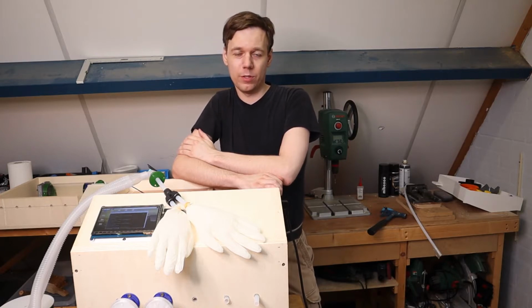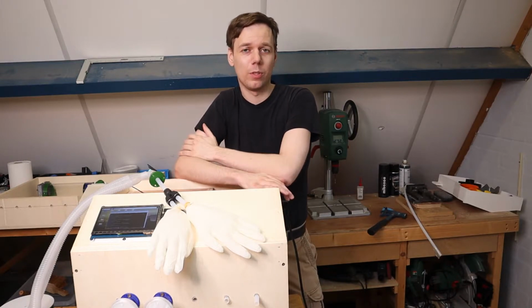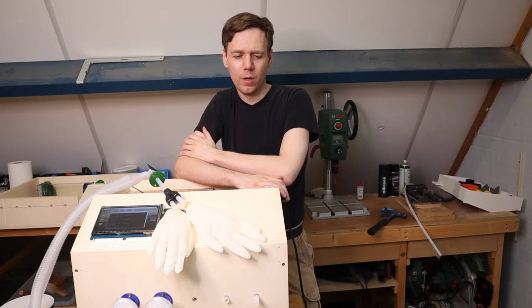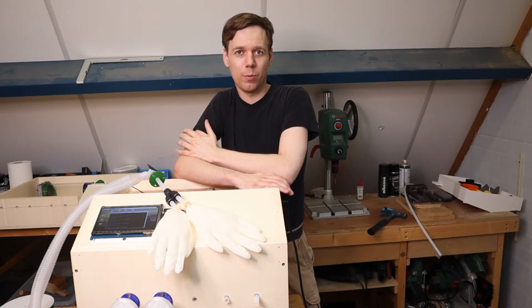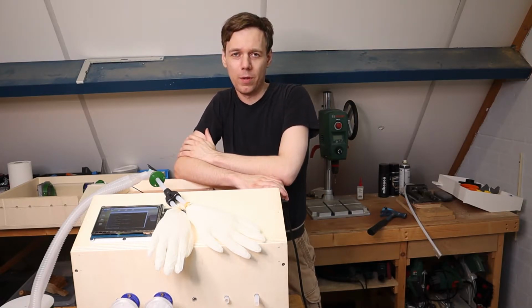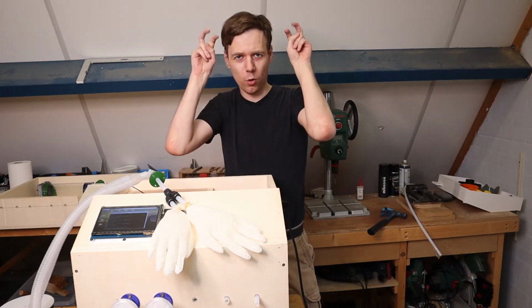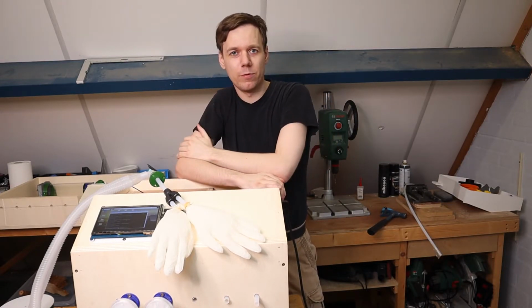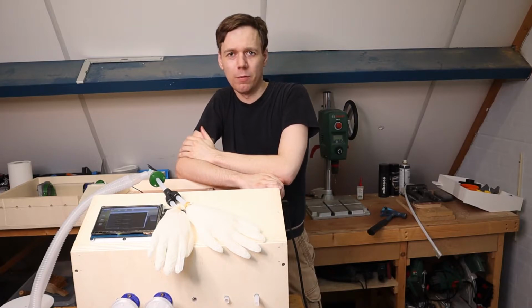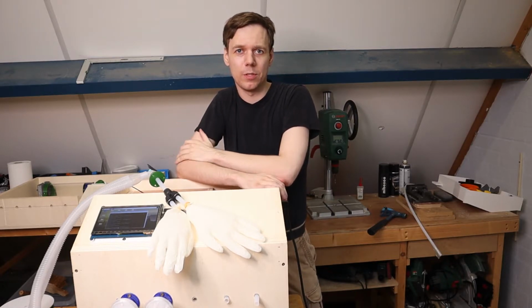The flip side of this is that ventilators are usually constructed out of custom bespoke components, because that's what gives you the best performance. However, if you try to ramp up production, you run into the issue that the parts simply aren't there. Remember when Medtronic open sourced their PB560 ventilator? None of them were built. None. The parts to do it simply don't exist.